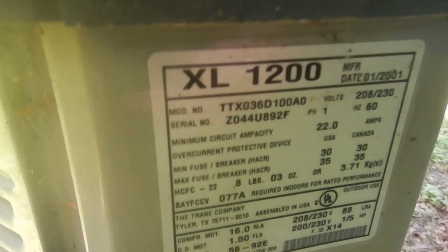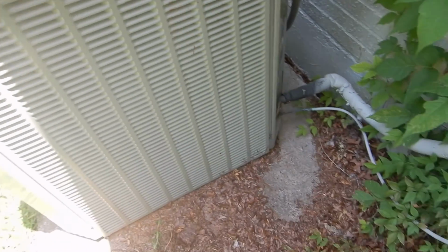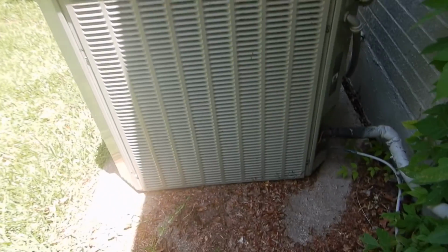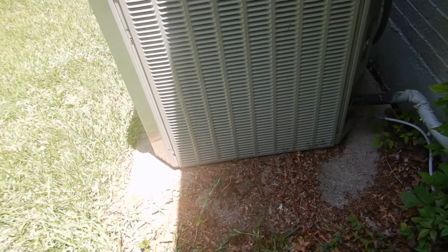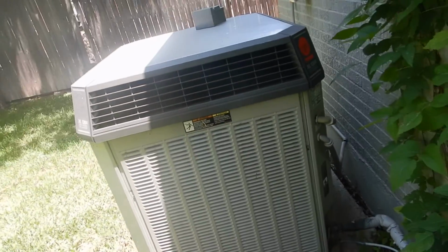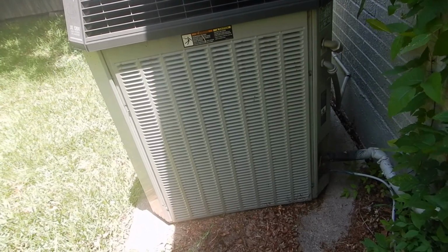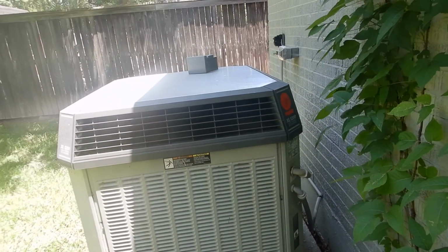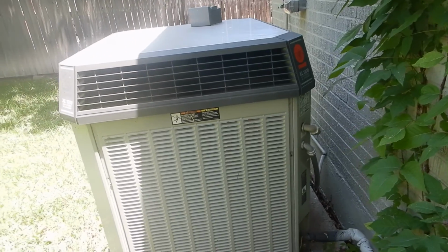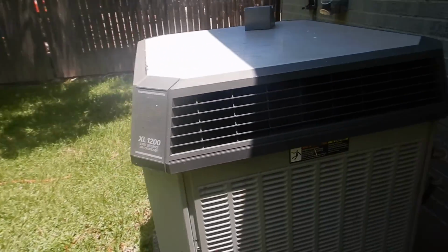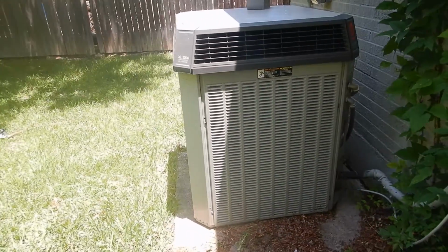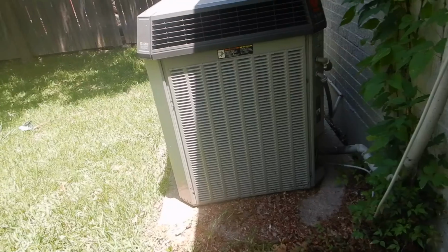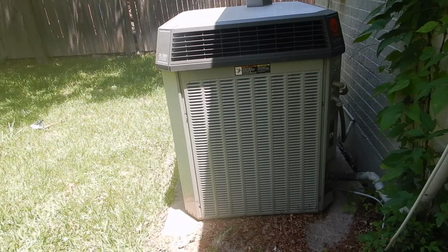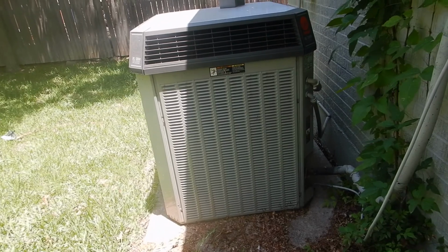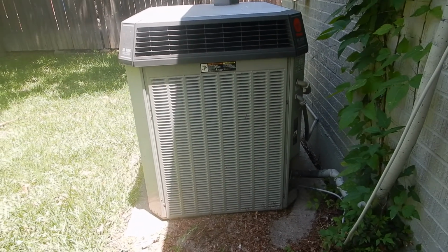We've got our data plate here. Okay, got a still image of that. And what this tells us is that this condensing unit was manufactured in 2001. That makes it 21 years old. This equipment is engineered on paper to last 20 years. It might last 35, but Las Vegas is going to give you 14. After about 14 years, air conditioning equipment in this part of the country is giving it up. This is like a SEER 12. Now we're getting SEER 14s and up, so it's not as efficient as it used to be.